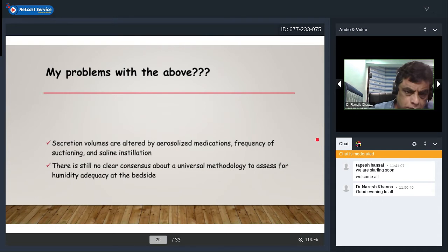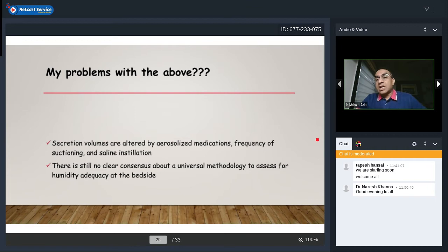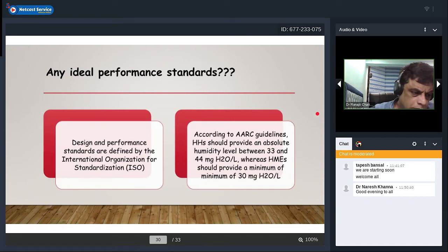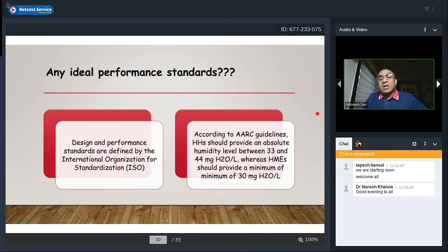Problems with these surrogates: secretion volumes can be altered by aerosolized medications and frequency of suctioning. There is still no clear universal methodology to assess humidity adequacy at the bedside. Performance standards are defined by ISO: heated humidifiers should provide 33–44 mg water per liter absolute humidity, and HMEs should provide a minimum of 30 mg water per liter.